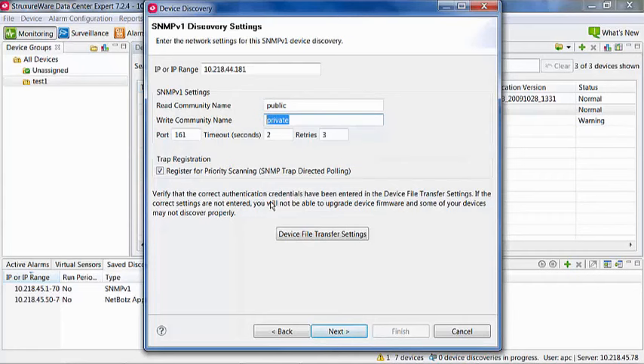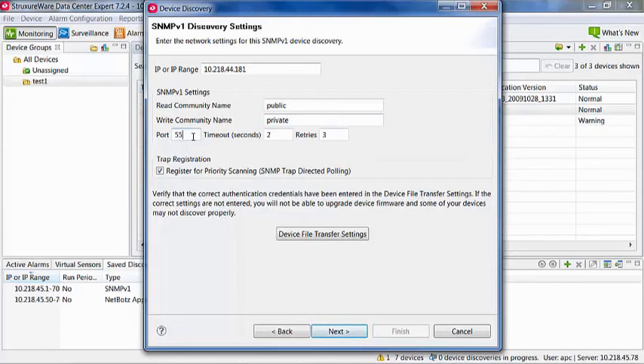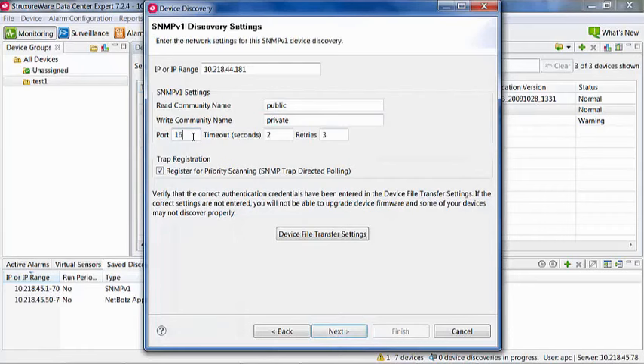Port 161 is the default SNMP port and is normally used. If your device has a non-default port configured for SNMP version 1, you must configure StruxureWare to use that port for this discovery and later polling using this field.